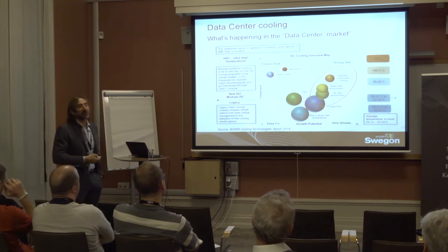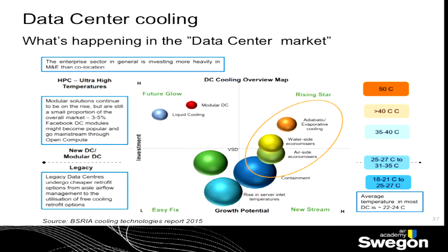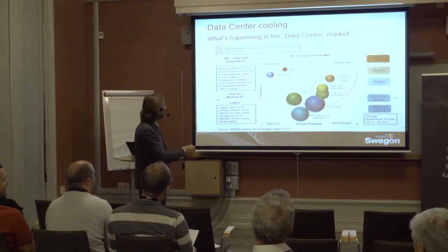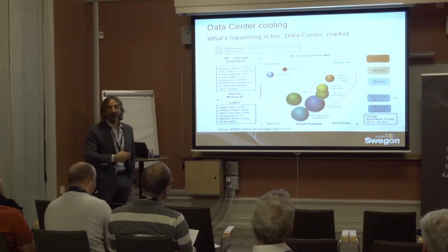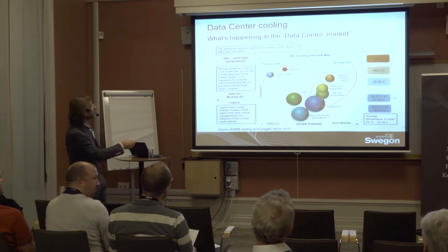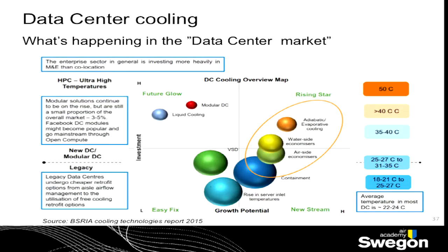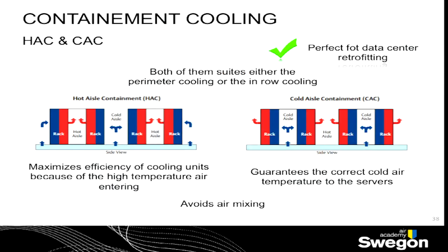But if we look at what's happening in the data center market, is this, more or less, okay? This is taken from the BSRIA analysis. And you see that, in terms of growth potential, the containment, the air side economizer, water side economizer, and the adiabatic evaporative cooling, or acrobatic cooling, as our friend likes to name it, are increasing a lot. Liquid cooling, too, is increasing quite a lot, but it's just dedicated to a particular technology, and so we want to focus on this side. For containment cooling, we can have both systems.